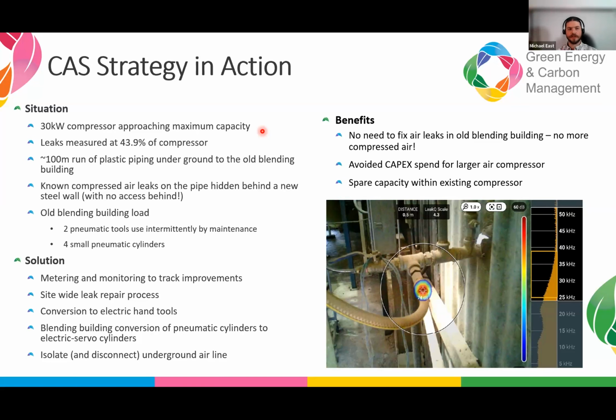Potentially as this progresses and evolves, they'll have spare capacity back, but then you'll have a load-unload machine operating at part load. So there should be room for variable speed drive controls, and potentially fine-tuning pressure as well once the leaks are fixed and we've isolated some of the piping.